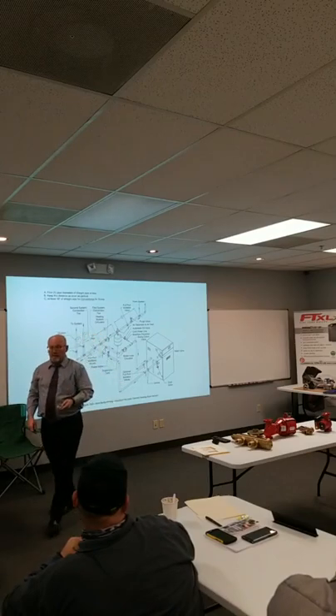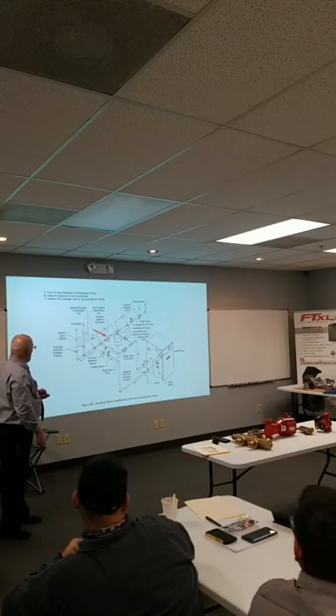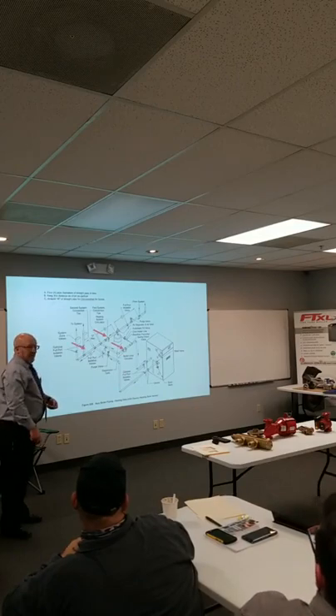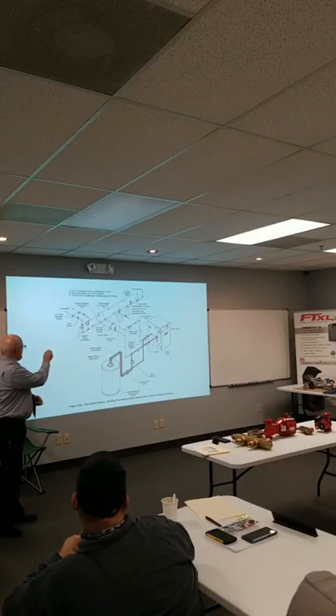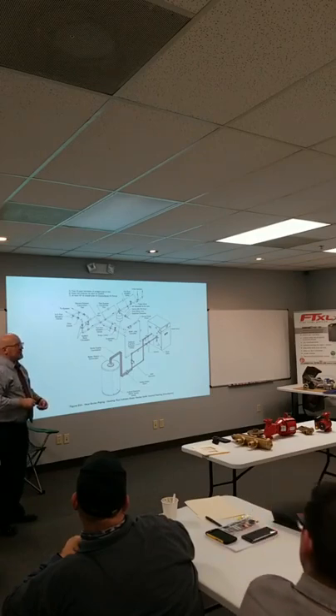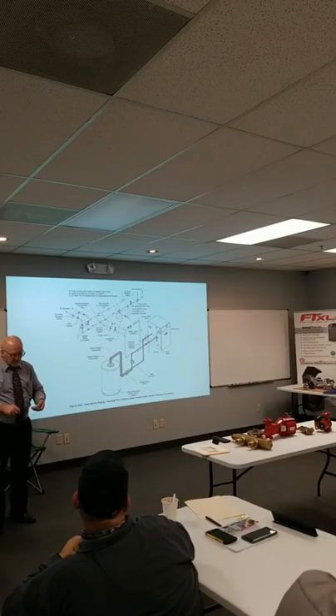So this drawing, as I show with these cool arrows, I did figure out how to do this, is actually wrong, okay? The pump needs to move over to the A position? It needs to be over there, yes. Okay, that's a better system. The next slide actually has zone pumps, and they're in the right position. They're on the outlet side of my supply coming from my boiler to my system. This is what I'd rather see, okay? Still pumping away from my point of no pressure change going out to the system. Does that make sense, guys?